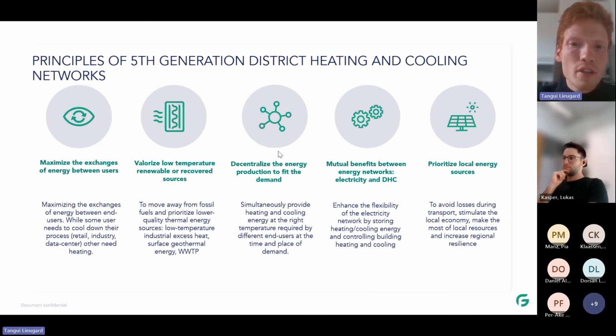The third principle is to decentralize the energy production to fit the demand. For example, if a building is efficient with good insulation and equipped with a floor heating system, it will only require 40 or 50 degrees to heat up. With this DHC, the heat pump is able to produce heat at the right temperature level and not above, which enhances the COP of the heat pump.